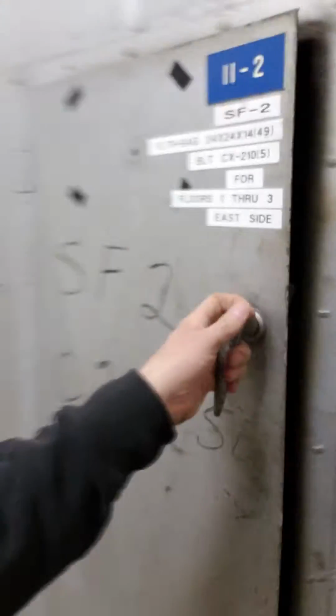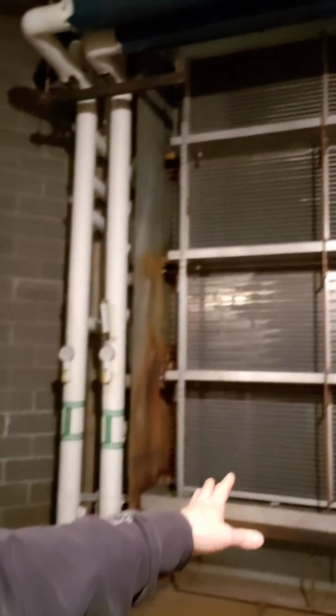This is going to be your air machine. We'll take a quick look inside. Inside you get a mixture of fresh air, return air, and supply air. Here you're supplying, there's a set of chill water coils right here. And behind that set is your set of hot water coils.